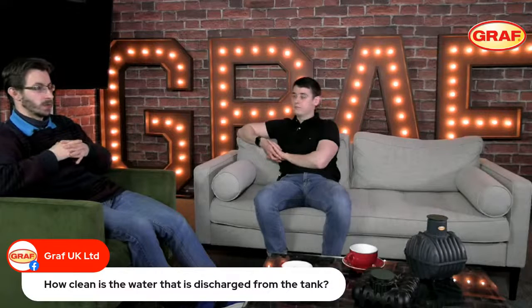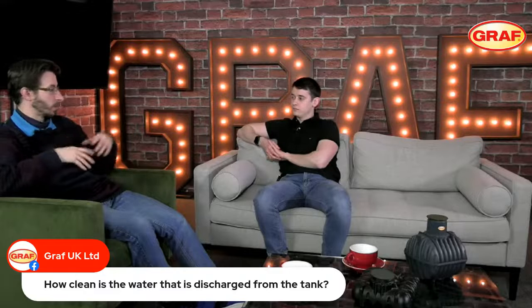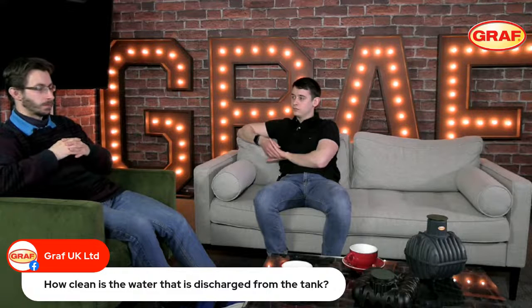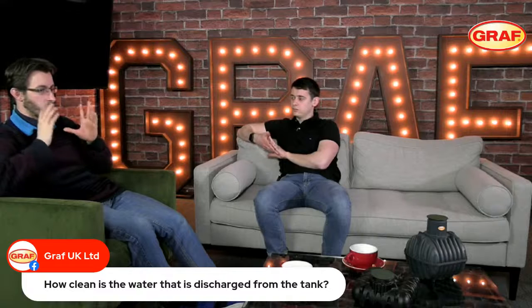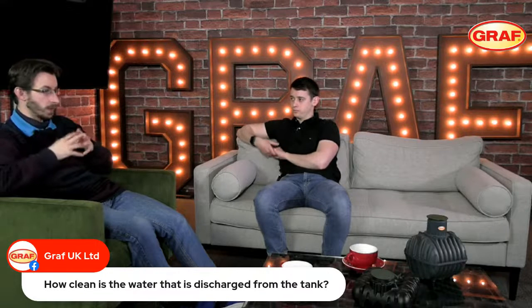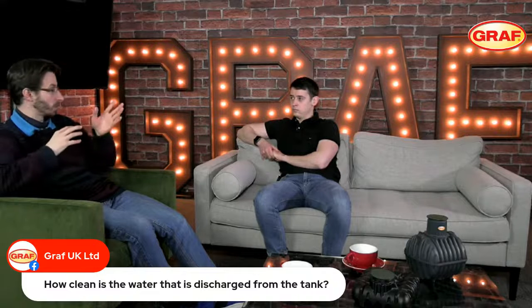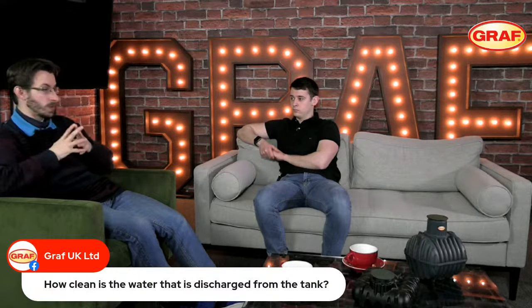This is generally affected, of course, within the treatment process itself, whether it be one of our SBRs or a competitor's treatment process. So it could be an SAF, it could be rotational disc, whatever it may be. We generally look at, of course, the quality of water achieving the parameters set out by British Water, which is generally 20 to 30 to 20, which we've mentioned before on this channel, where we talk about the concentration of the BOD being 20 milligrams per litre in the effluents for BOD, suspended solids at 30 milligrams per litre, and then the ammonia at 20 milligrams per litre. So those are the general parameters we look to. Most treatment plants will conform way better than that.